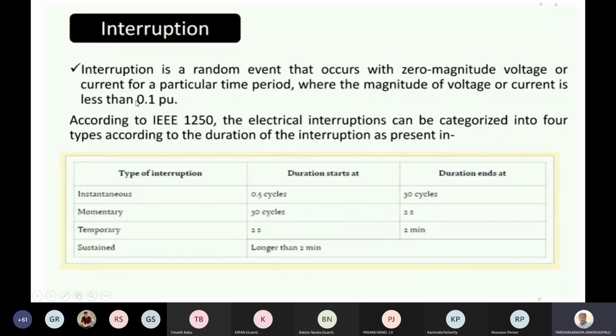One more thing is interruption. Interruption is a random event which occurs with zero magnitude voltage or current for a particular time period, where the magnitude of voltage or current is less than 0.1 per unit. We have different standards: sag, swell, under voltage, over voltage. Sag starts from 0.1 magnitude, so if it is below 0.1 per unit, whether voltage or current, it is said to be interruption. According to IEEE 1250, electric interruptions can be categorized into four types, which we already discussed in the previous slide: instantaneous, momentary, temporary, or sustained.